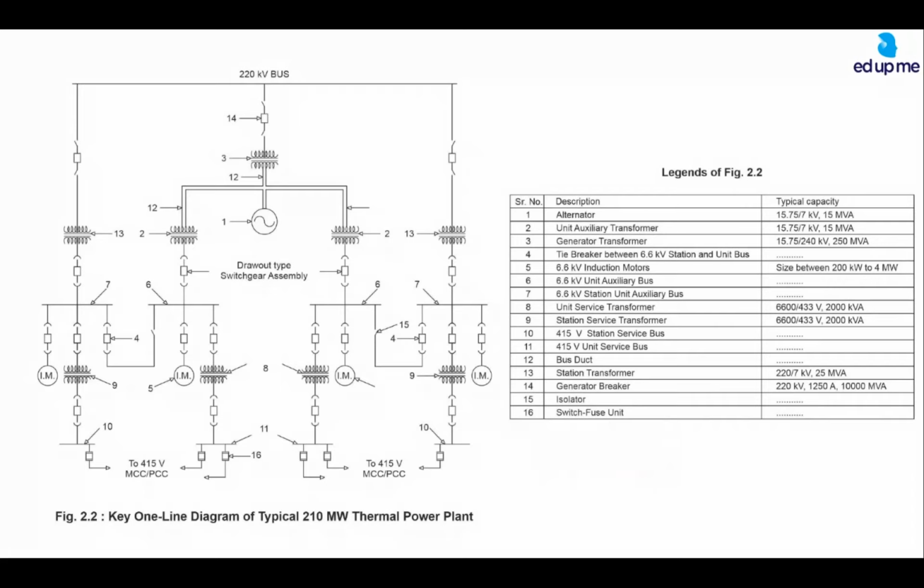But there are many station auxiliaries also, like coal handling plant is a station auxiliary. CW system, circulating water system, is a station auxiliary. Station auxiliary means the auxiliaries which are common to all the units in a plant. Say in Vanakbori, there are 7 or 8 units. There are certain auxiliaries which are common to all units, and certain auxiliaries which are specific to a unit. They are known as unit auxiliaries. PA fan, ID fan, FD fan, BFP are unit auxiliaries. CW system, coal handling system, they are station auxiliaries. These station auxiliaries are fed by the station bus. Station bus power is coming from the infinite bus. From 220 kV to 6.6 kV, the power will come to number 7. And that many motors will run on that.